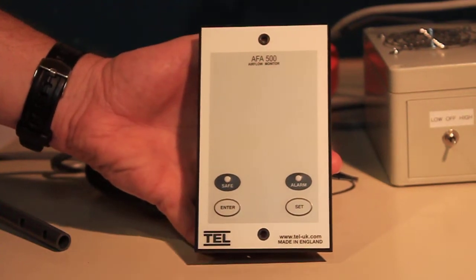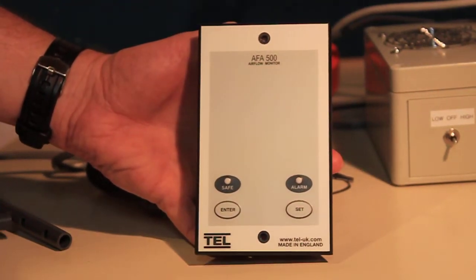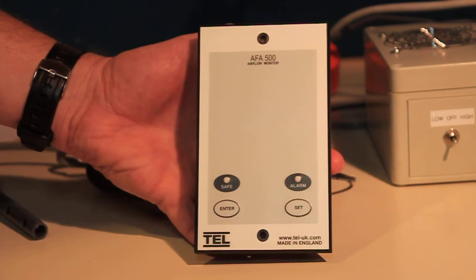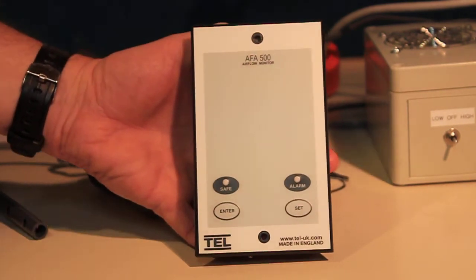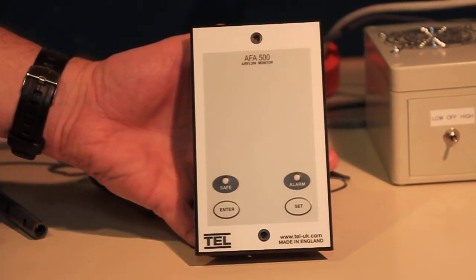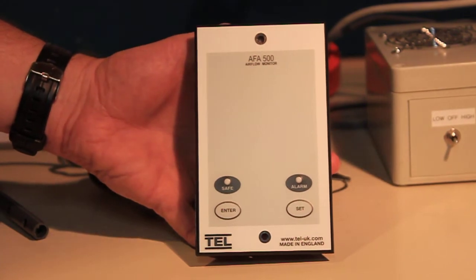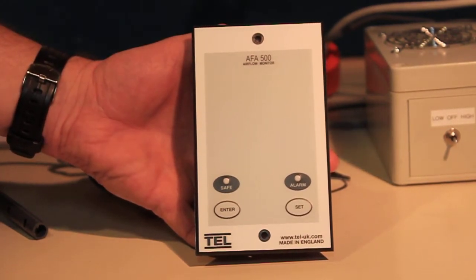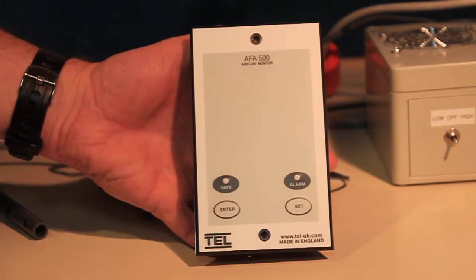The AFA 500 BSC is the most widely used biosafety cabinet monitor in the TEL product line. It has a green safe light for normal airflow conditions and a red light and horn for alarm conditions. It requires a simple, single-point calibration via push-button process.